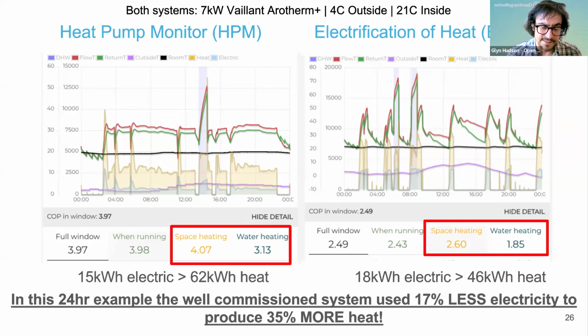So you can clearly see that this is the system on the left from HeatPumpMonitor. It's running at quite a low, steady flow temperature, trickling heat into the property throughout the day. In this example, it's running at 32-degree flow temperature, trickling about 2.5 kilowatts of heat into the property, whereas the system on the right is running quite sporadically. Every time the heat pump comes on, it works really hard to raise the flow temperature up to about 55 degrees, and then it switches off again. That's not the most efficient way to run a heat pump. Low and slow is the best way, and that results in significantly improved performance. You can see the system on the left achieved a space heating efficiency of 4, whereas the one on the right from electrification of heat only achieved a space heating efficiency of 2.6.